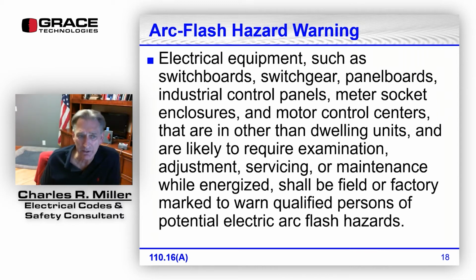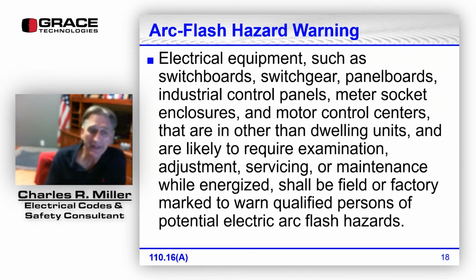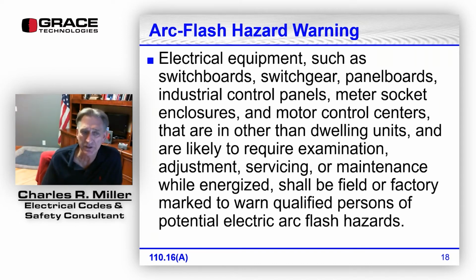that are in other than dwelling units and are likely to require, here's the, okay, this label is not required in dwelling units, at least not yet. But it gives us an idea of the equipment above: switchboard, switchgear, panel boards, industrial control panel, meter socket enclosures, motor control centers. These are examples. It's not all inclusive. But the key part is, is it likely to require examination, adjustment, servicing, or maintenance while energized? Then, if it is, it has to be field or factory marked to warn qualified persons of potential electrical arc flash hazards.